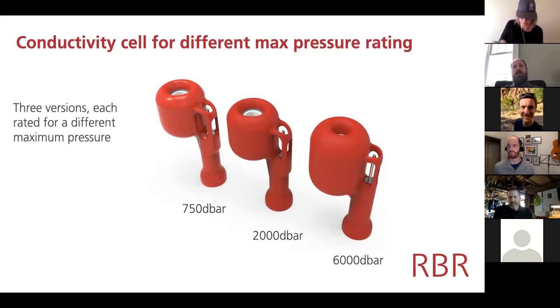And the reason is that you're changing the geometry of the cell, but you're not doing so once and for all time. Most of that material is going to slough off over the months that it's in the water, and so the geometry will change. It's one thing to put on a coating where you can calibrate out the effects, but the coating doesn't change. But if that coating effect changes over time, then you're really in trouble. The same is true even of copper-based paints. Apart from the whole question of how conductive the copper-based paint is, and whether you're bypassing the electrical circuit by basically giving it a short circuit to get back, most copper-based paints also slough off over time, as those of you who have to anti-foul boat bottoms know well. So generally, we wouldn't recommend anything like that.